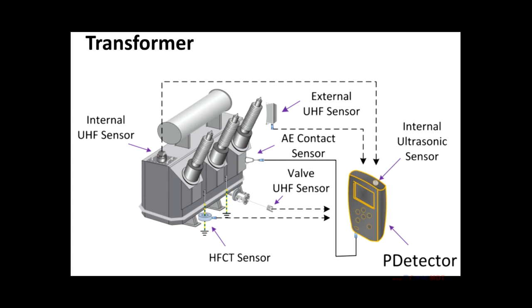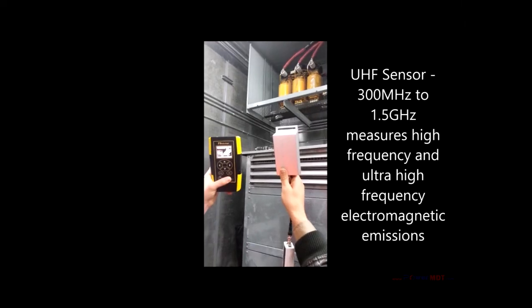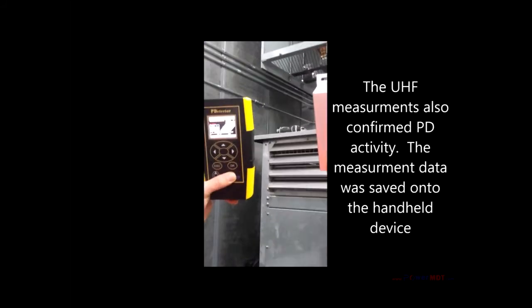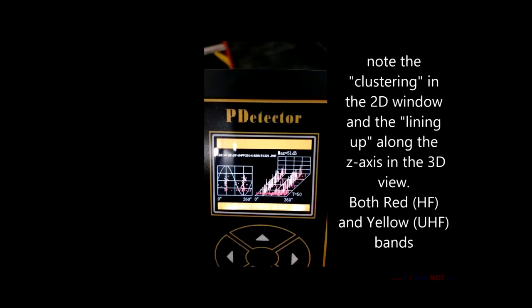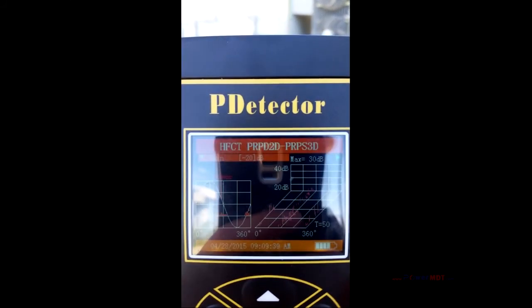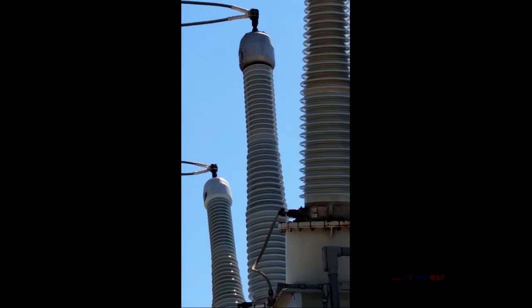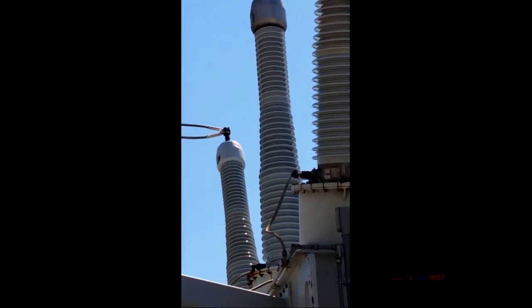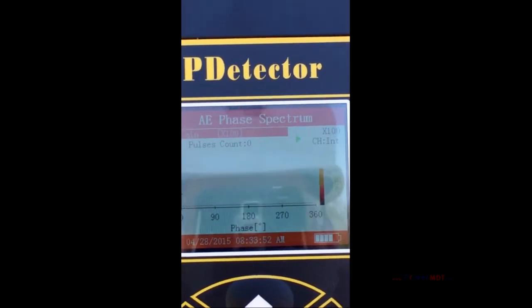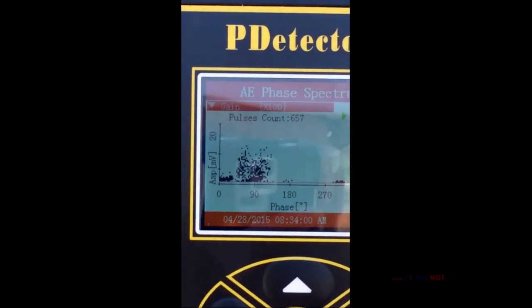No matter which device you're testing, you'll be able to use at least three sensors to get a complete picture of the insulation condition. First, use the UHF sensor to check for airborne radio frequency signals. Then apply the HFCT sensor around the ground lead of the apparatus — any nearby PD will induce high-frequency current pulses onto the ground lead which can be measured with the HFCT. Then use the ultrasonic sensors: the dish concentrator to measure airborne acoustic emissions, and the acoustic contact sensor to measure in-tank acoustic signals. If there's an insulation problem, the PDtector will find it.